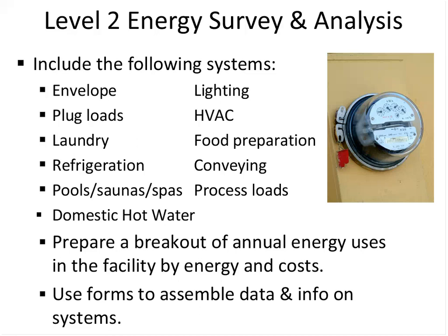And CDAC, on our website, we have what we call energy fact sheets, and we talk about what you can do in different types of buildings. So we have a whole set of these, and we do have one for pools and spas and that type of thing where you can save energy. Domestic hot water, what's the temperature of the water? In many cases you can turn that temperature down. You can also turn water heaters off at night when they're not being used, especially if there's a circulating hot water pump. You may want to put that on a time clock.